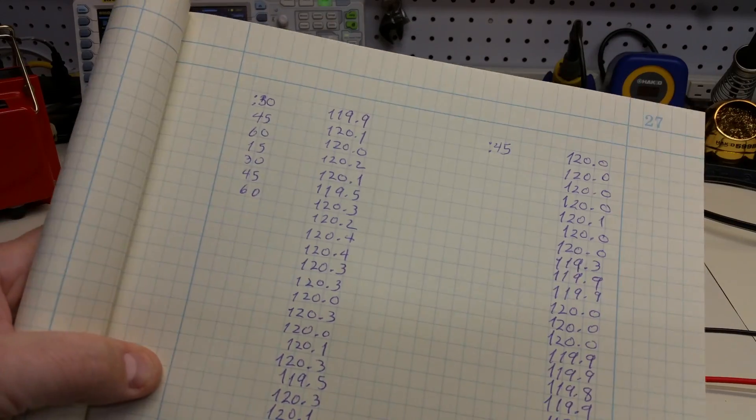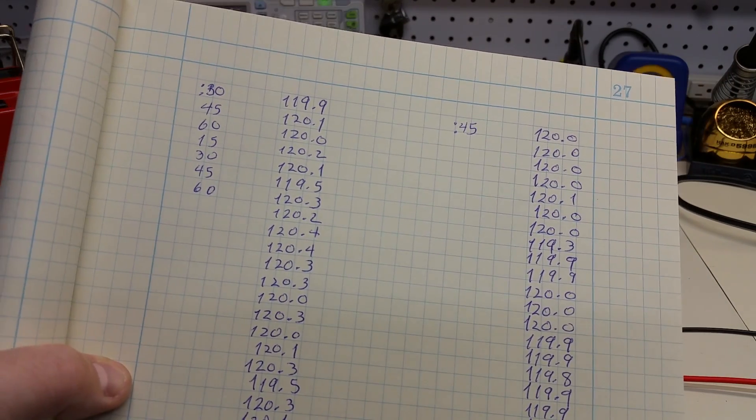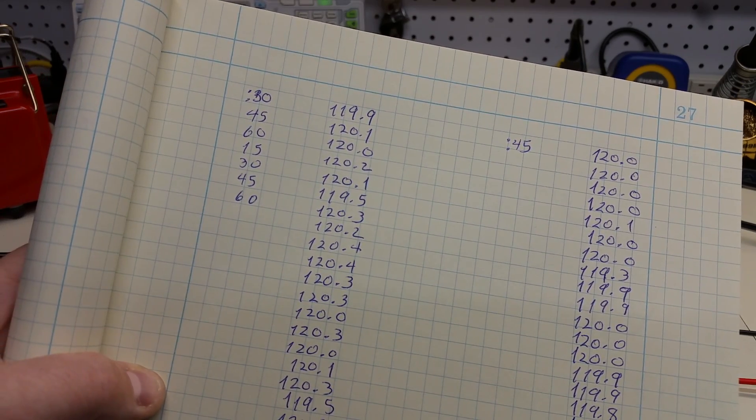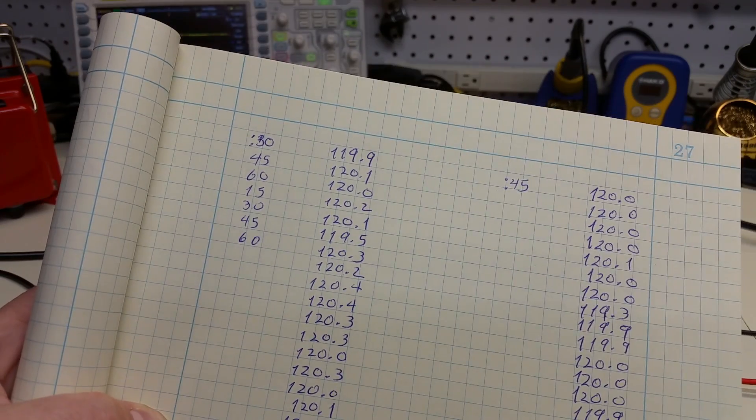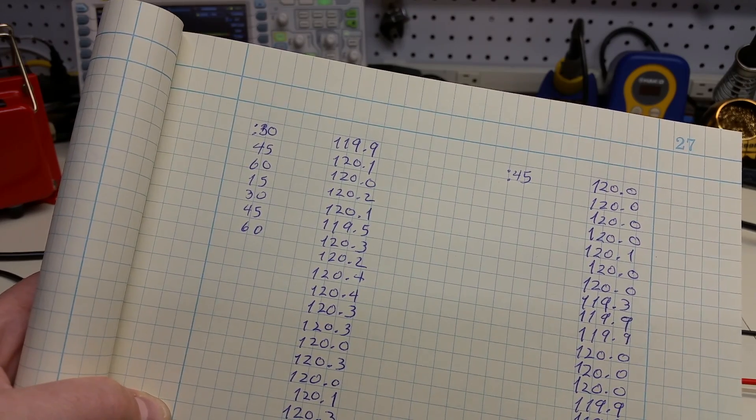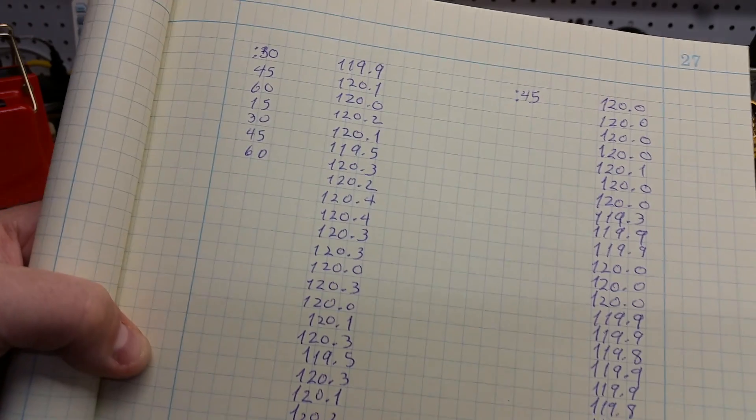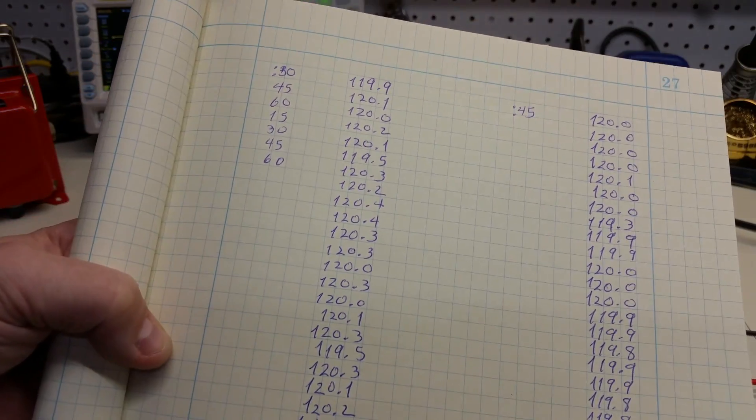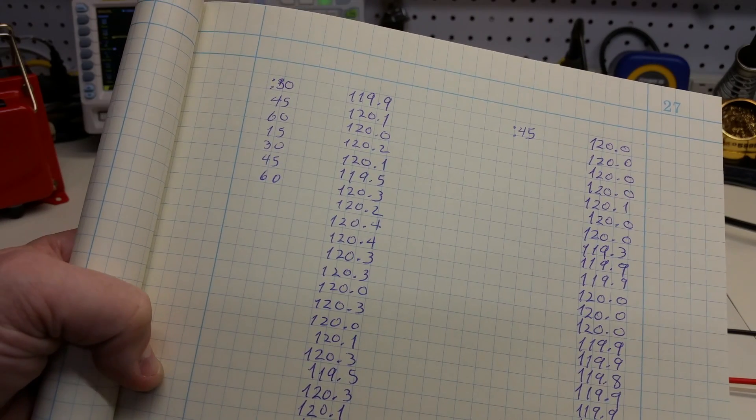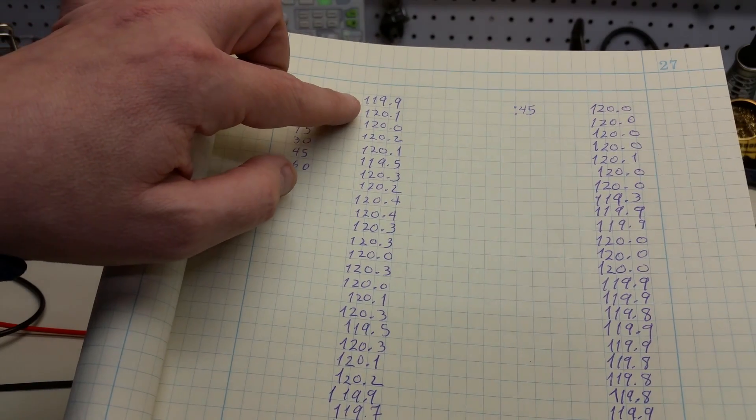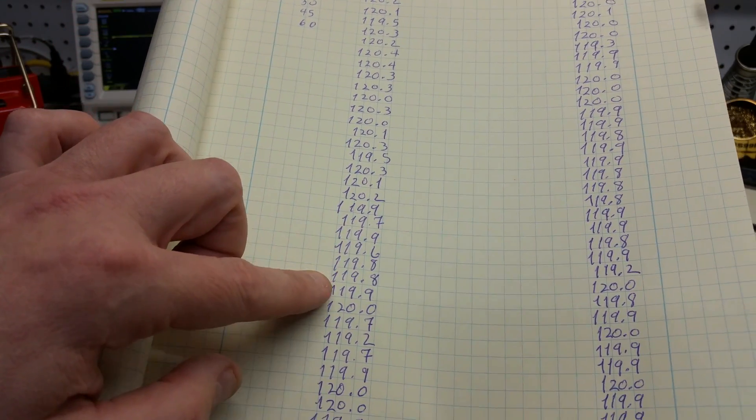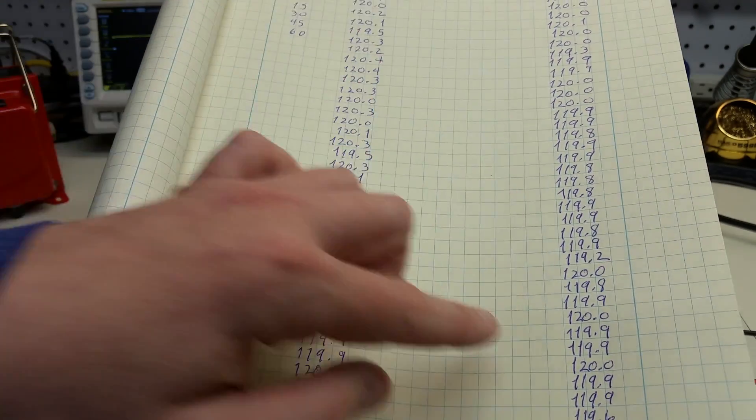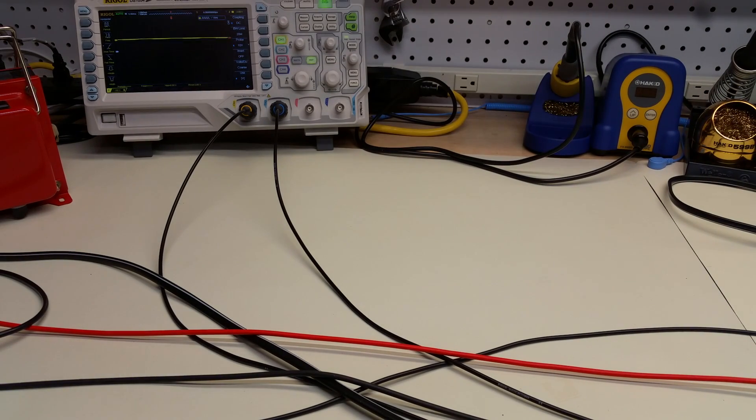At the beginning of the video, I showed a screenshot for the course of a minute or a minute and a half of a bench voltmeter. Probably noticed it just kind of informally wobbling and changing over the course of the time of the intro. Well, I did an experiment where every 15 seconds, I wrote down the voltage reading. And I did that for about 20 minutes. This is the data that I collected. This is meant to be illustrative. This is not out to a gazillion decimal points. It's kind of interesting. First thing you notice is that, in fact, it does wobble. You go from the 119 range to the 120 range, kind of stays in the 120s for a while, and then it goes down to the 119s for a while, and then it kind of goes back up and so on and so forth.